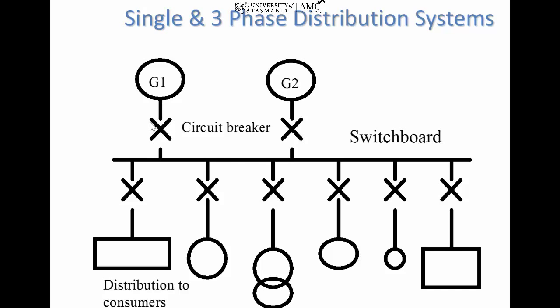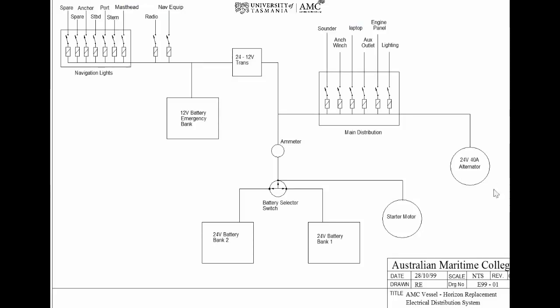Here we're showing an X as a circuit breaker, so a circuit breaker from each of the generators through to our main bus bar or switchboard, and then from there through other circuit boards to our distribution network or sub boards, and here we've got other load consumers. This one with 2 circles intertwined shows a transformer, and here's another system, a distribution system. This one's all DC though, so the alternator is actually producing DC, 24 volts DC, and this is going through to our main distribution system, shown through a fuse and a circuit breaker to our different loads, and it's also got a battery system which is also 24 volt DC, so batteries in series parallel to supply our main distribution as well if the alternator stops or the main engine stops.